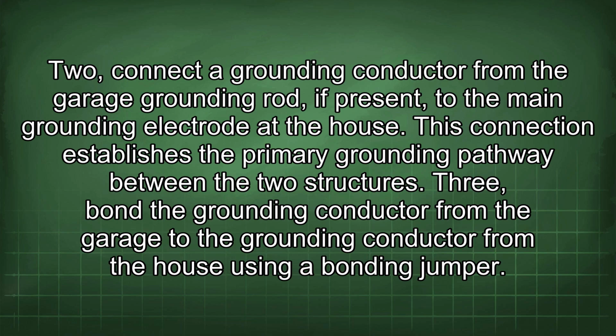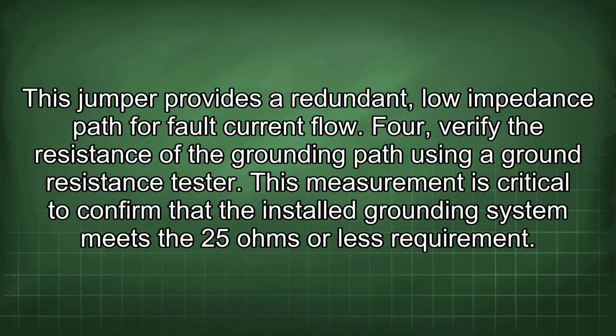3. Connect the grounding conductor from the garage to the grounding conductor from the house using a bonding jumper. This jumper provides a redundant, low impedance path for fault current flow. 4. Verify the resistance of the grounding path using a ground resistance tester. This measurement is critical to confirm that the installed grounding system meets the 25 ohms or less requirement.